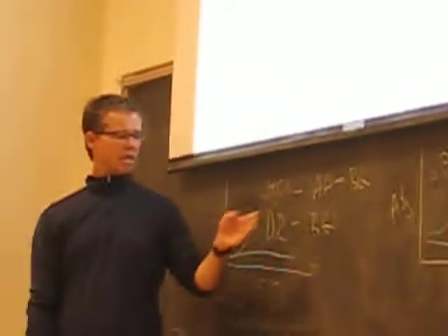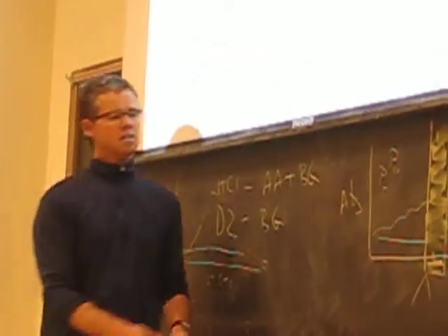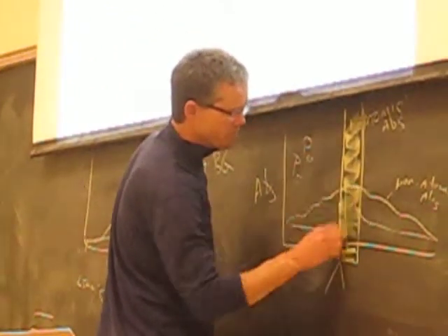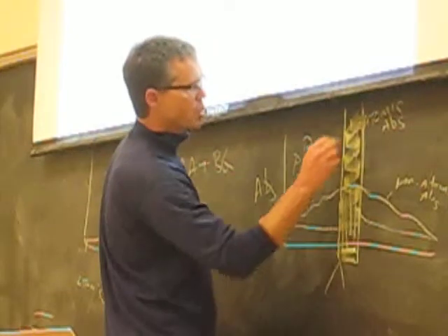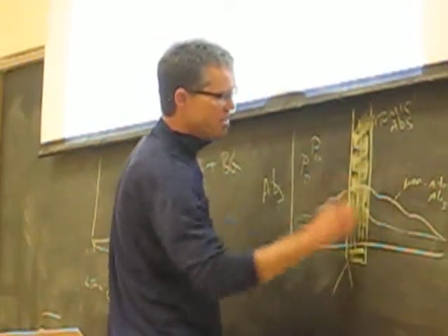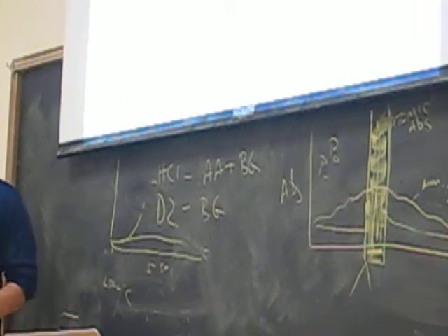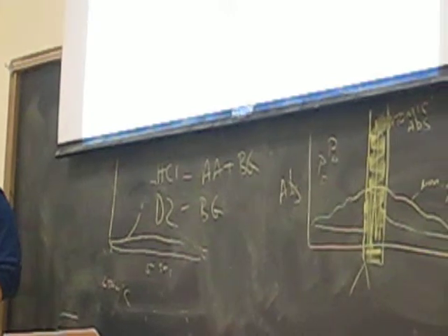And then the instrument is actually doing a subtraction. So when just the D2 is going through, it's just measuring this part. When the hollow cathode is going through, it's measuring all this. And by subtracting the two, it's able to get a measure of what is truly, they think, atomic absorption, separate of the background. But your instrument doesn't have that on it because it costs more money.